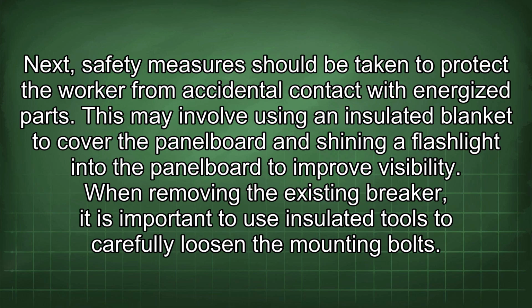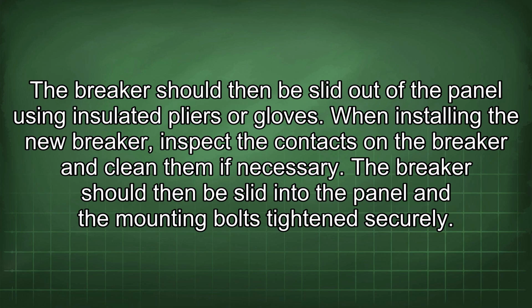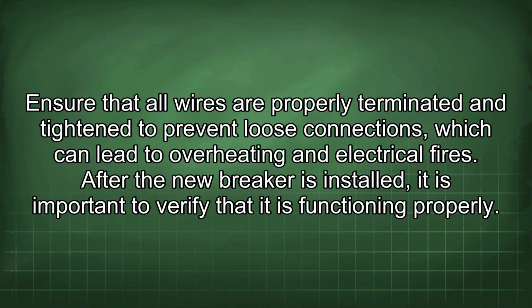When removing the existing breaker, it is important to use insulated tools to carefully loosen the mounting bolts. The breaker should then be slid out of the panel using insulated pliers or gloves. When installing the new breaker, inspect the contacts on the breaker and clean them if necessary. The breaker should then be slid into the panel and the mounting bolts tightened securely. Ensure that all wires are properly terminated and tightened to prevent loose connections, which can lead to overheating and electrical fires.